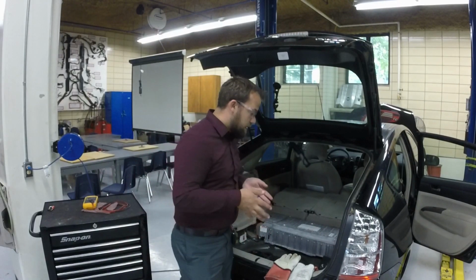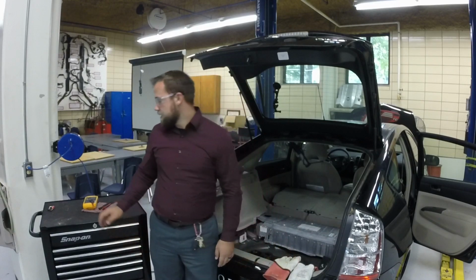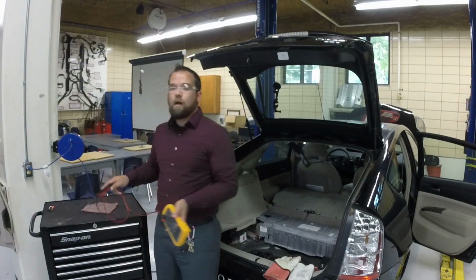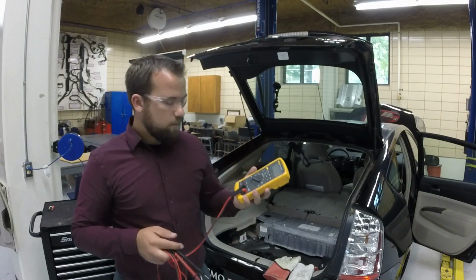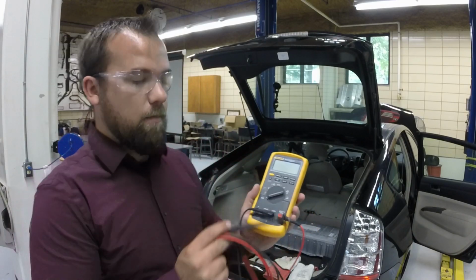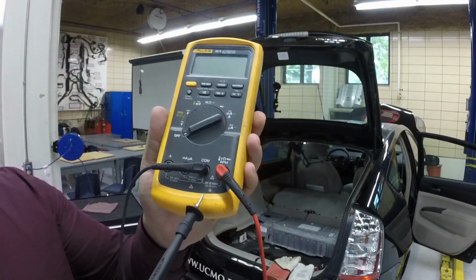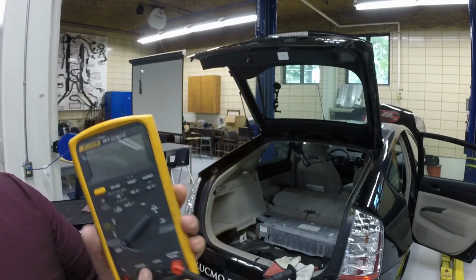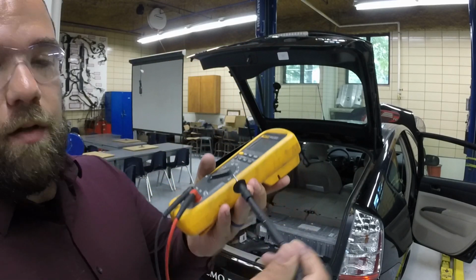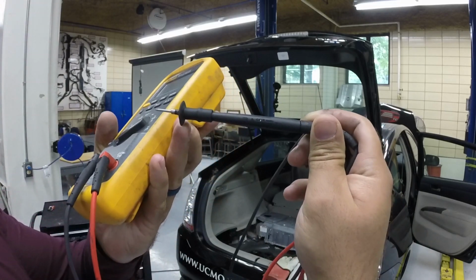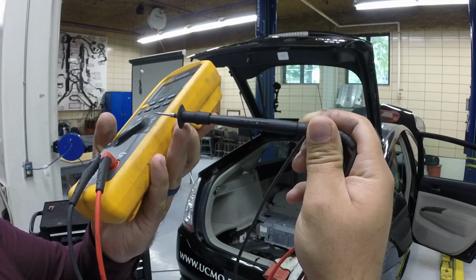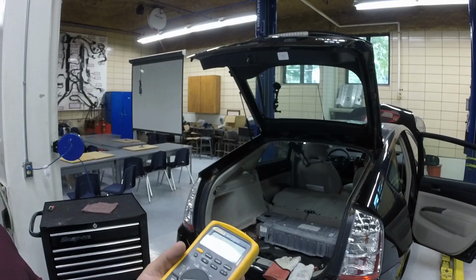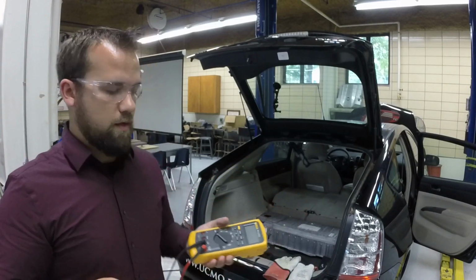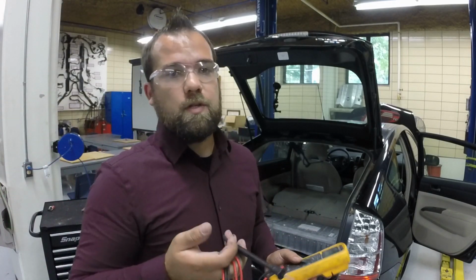There's a couple things I'm going to need in addition to my safety gloves. I'm also going to need a CAT III, 1000-volt multimeter. You can see on the bottom, right here, CAT III, 1000-volt rated multimeter. You'll also notice these leads are rated Cat 3, 1000-volt. So this meter and the leads are safe to use on a hybrid application with voltages up to 1000 volts.